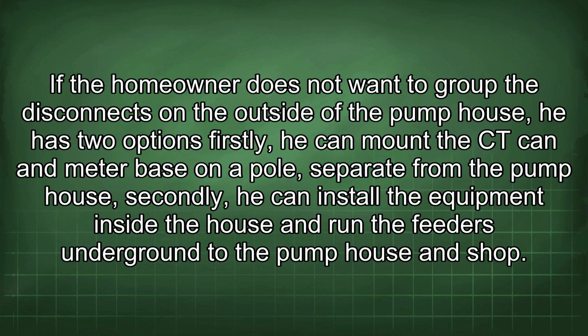If the homeowner does not want to group the disconnects on the outside of the pump house, he has two options. Firstly, he can mount the CT can and meter base on a pole, separate from the pump house. Secondly, he can install the equipment inside the house and run the feeders underground to the pump house and shop.